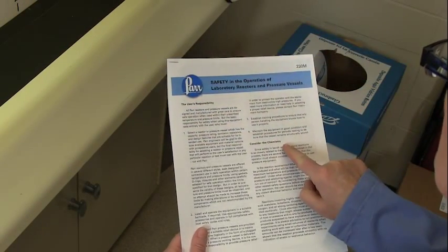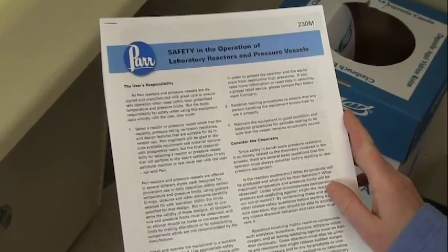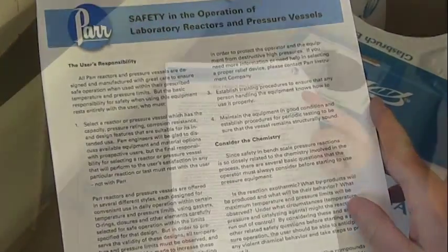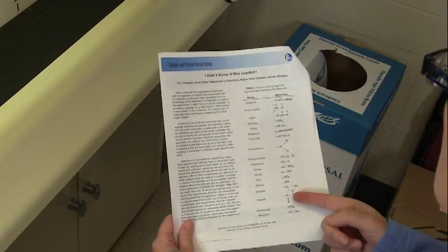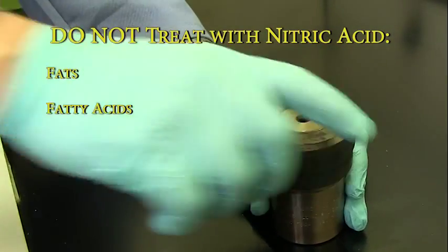Always evaluate the chemistry that you are trying to achieve with special consideration for gaseous byproducts that may affect the pressure inside the vessel. Some chemicals are prohibited from use in pressure vessels.